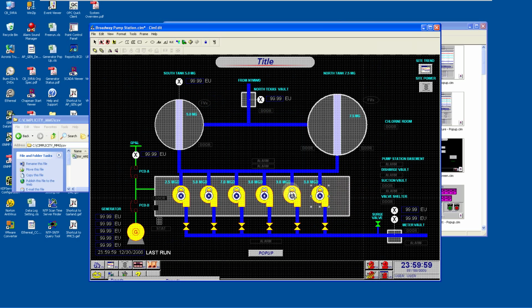And therefore, there's one central location where you have all the information for the scaling, the pump signals, the valve signal. They're all in one place where your I/O will never get messed up, because you always originated all your points and all your objects for Simplicity and for PLC from one file, the memory map for that particular pump station. That keeps everything consistent and minimizes the room for error.